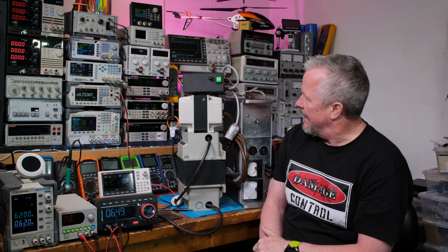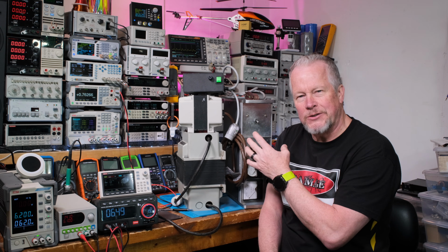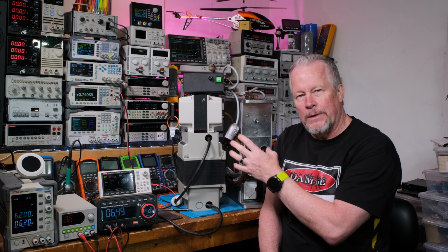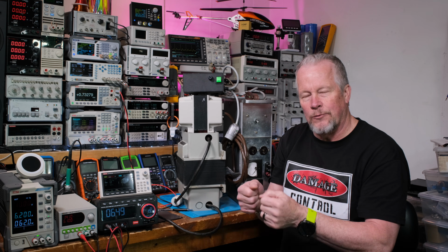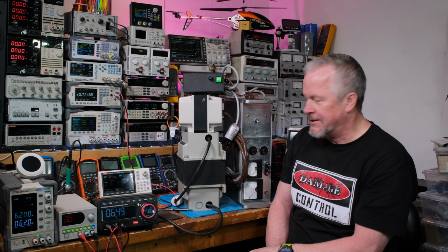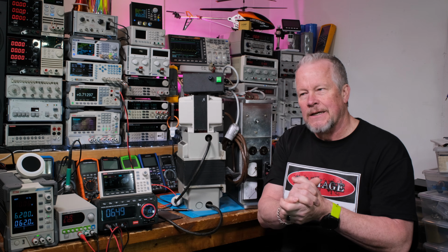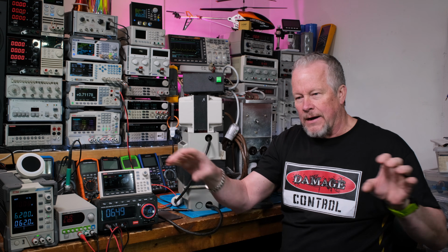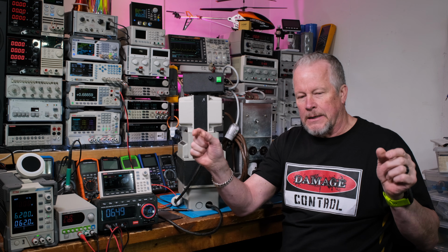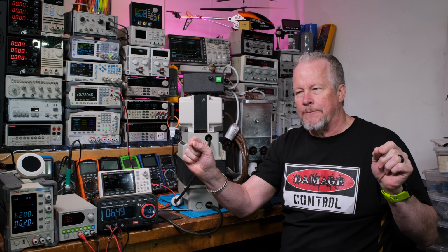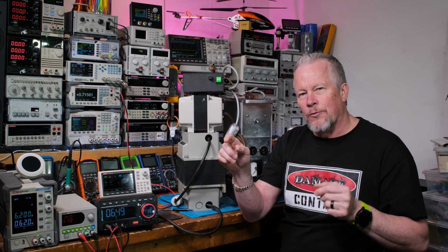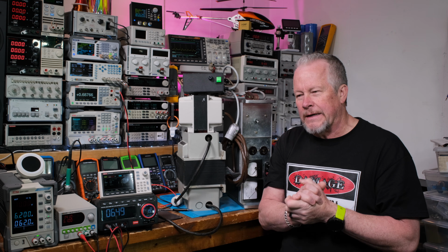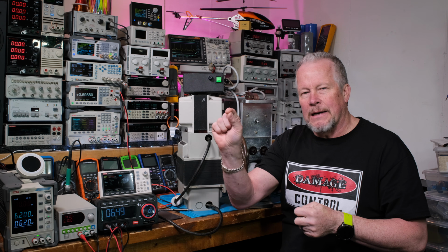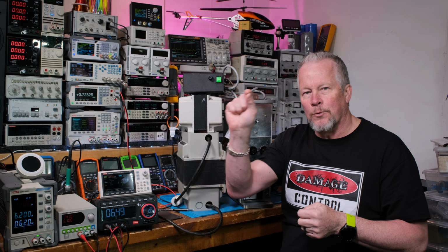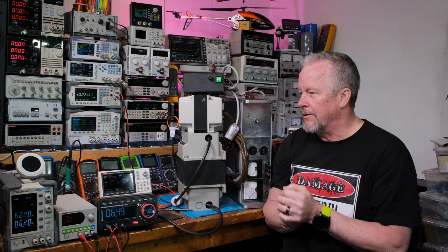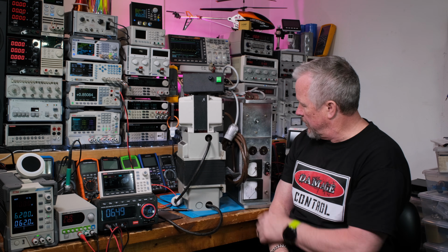Really nice. You have to check to make sure you have that floating secondary winding that's not referenced to chassis. It's still an isolation transformer, it's just the ground. On both sides, if you have three prongs, the ground will still be the same ground. But the key difference you want to look for is if they bond that ground to one of the two conductors on the connector. So you want to look for that.